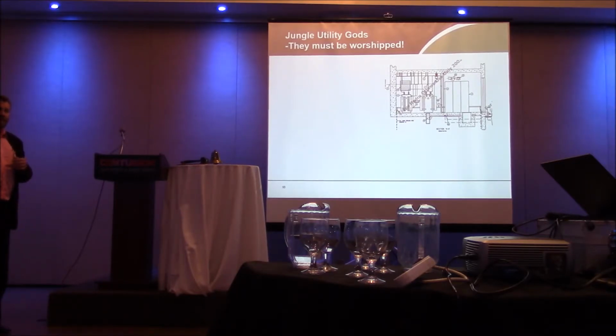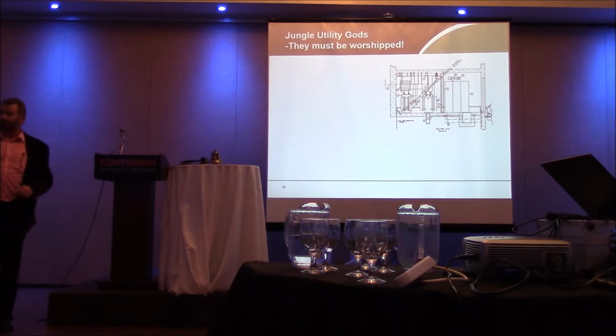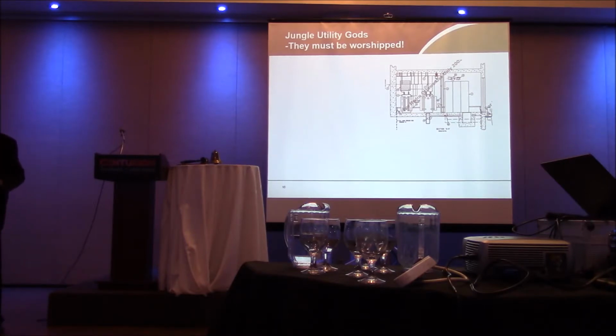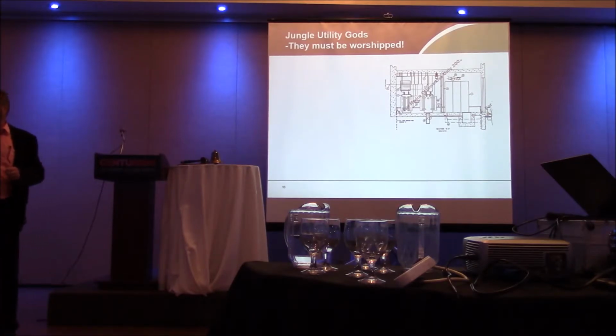If there's not a rain hood or some other device to keep the snow and rain out, during my service days I got called to an apartment building on an emergency. Hydro had opened the door to the vault, and there was a snowdrift about 4 feet deep that had blown in, building up inside the transformers. So I got paid to shovel snow in a hydro vault that day, and then fix the electrical components that had melted from the moisture.